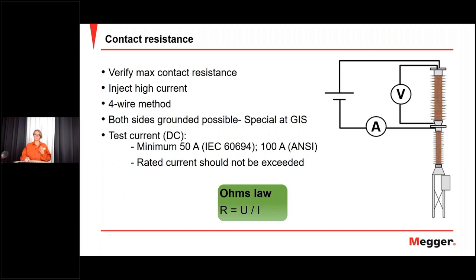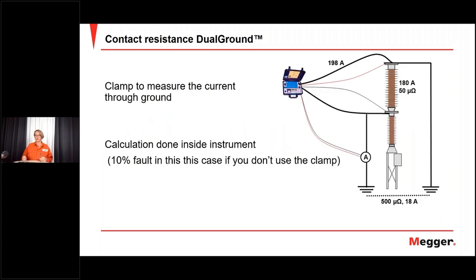And again, I mentioned contact resistance measurement, at least 50 amps, and American standards actually say 100. But also, both sides grounded is here much more important when you work outside. But on GIS, you really have to consider some things when you measure, because you have a very low resistance in the ground. If you do dual ground with outdoor circuit breakers, it's important to be aware that it's good to compensate for the current. Depending on the resistance, it can, of course, be possible to measure contact resistance with two sides grounded without compensating. But you must be aware of what you're doing here. You have to know that then you miss the component of the current flowing through ground. In this example, you will get a 10% fault. But this, of course, is a matter of the knowledge you have, how experienced you are, if you can consider not calculating on that.